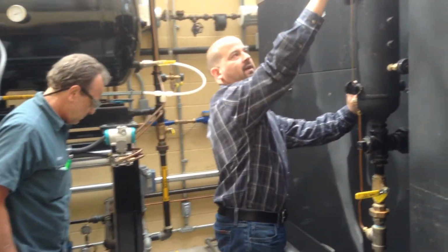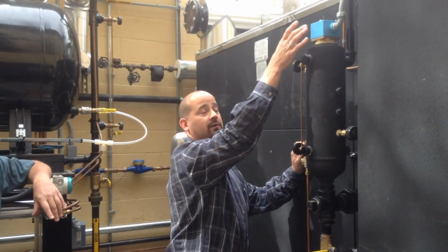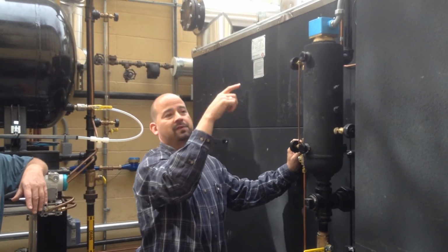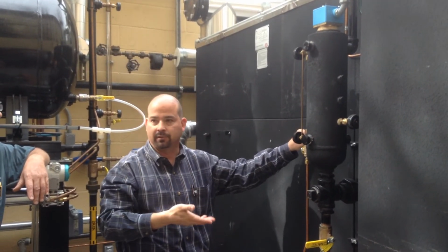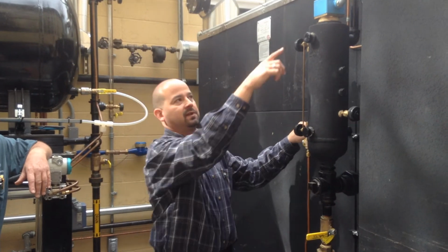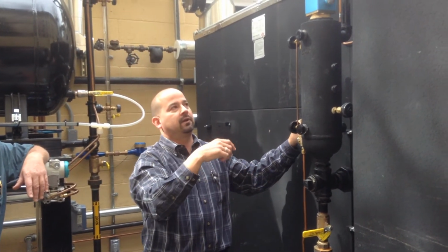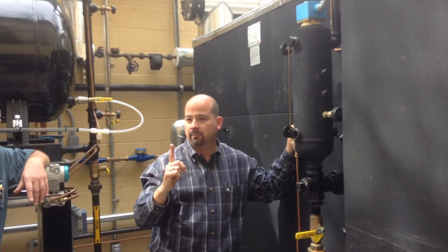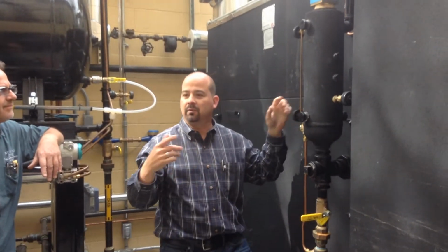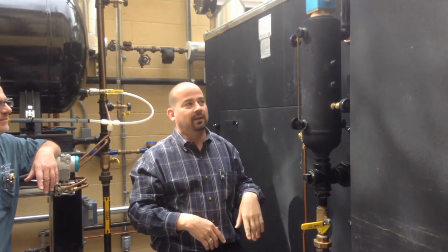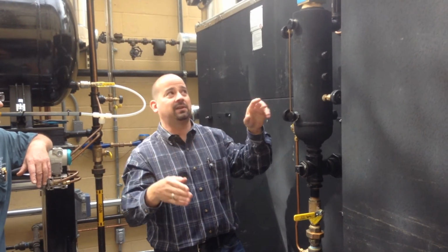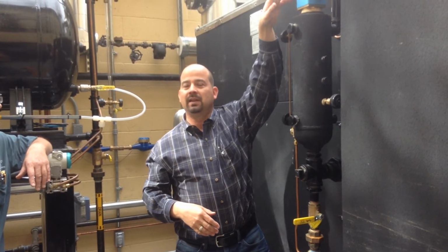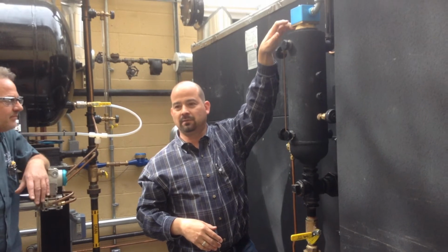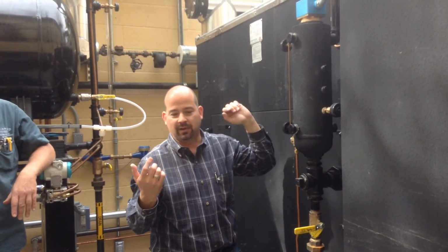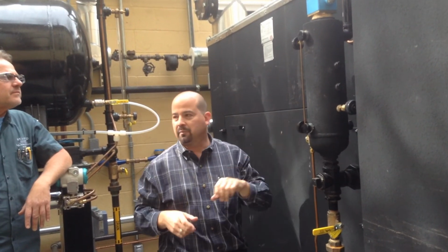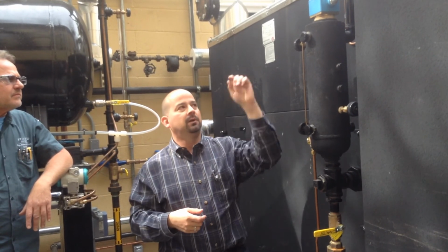You're going to want to take the cover off of this control here. This is the water level controller. And there's a series of what appear to be spark plugs. They're just level probes, porcelain probes with stainless steel 1/4-inch rods. You're going to want to take them out one at a time. Don't take them all out, because then you won't know which one, how long it was, where it went. Even though the wiring schematic is labeled A, B, C, D, and there are stampings on here, A, B, C, D, after 5 years of operation, this one gets a little fuzzy and you can't see it. So just do one at a time, you can't go wrong. Take it out, take some emery cloth, clean the stainless steel probe, put it back.